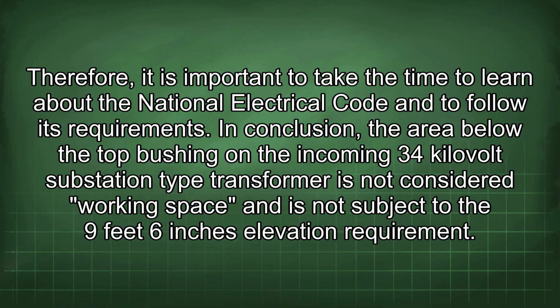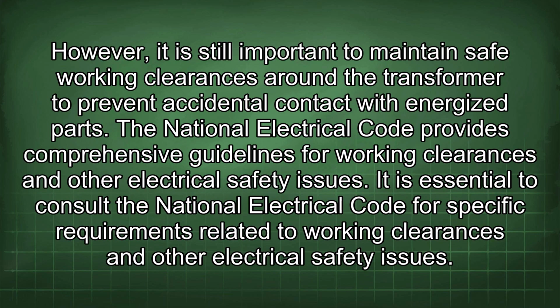In conclusion, the area below the top bushing on the incoming 34 kV substation type transformer is not considered working space and is not subject to the 9 feet 6 inches elevation requirement. However, it is still important to maintain safe working clearances around the transformer to prevent accidental contact with energized parts. The National Electrical Code provides comprehensive guidelines for working clearances and other electrical safety issues.